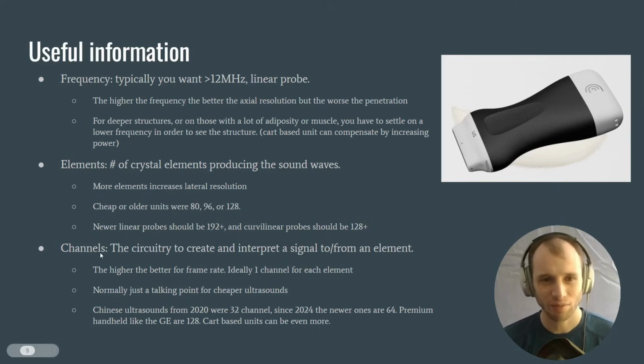Now channels. This is the circuitry to create and interpret a signal from an element. The more channels you have, the better the frame rate. The ideal number is 1 channel for each element. Normally, again, this is just a talking point for cheaper ultrasounds. Chinese ultrasounds from around 2020 were typically around 32 channel. Since 2024, newer ones are 64 channels. Premium handhelds like GE are 128 channels. Cart-based units can be even more.